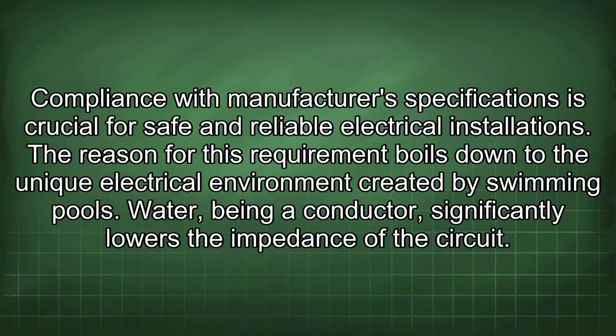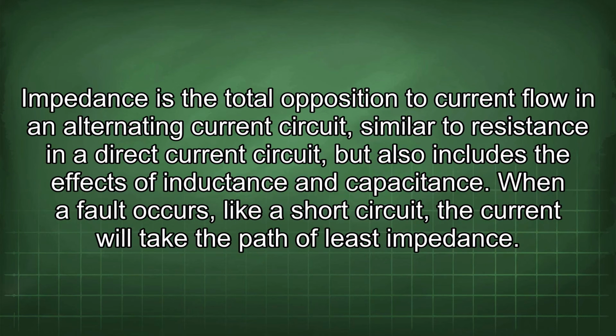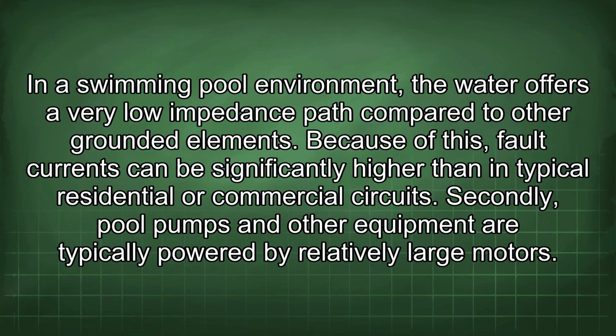The reason for this requirement boils down to the unique electrical environment created by swimming pools. Water, being a conductor, significantly lowers the impedance of the circuit. Impedance is the total opposition to current flow in an alternating current circuit, similar to resistance in a direct current circuit, but also includes the effects of inductance and capacitance. When a fault occurs, like a short circuit, the current will take the path of least impedance. In a swimming pool environment, the water offers a very low impedance path compared to other grounded elements. Because of this, fault currents can be significantly higher than in typical residential or commercial circuits.